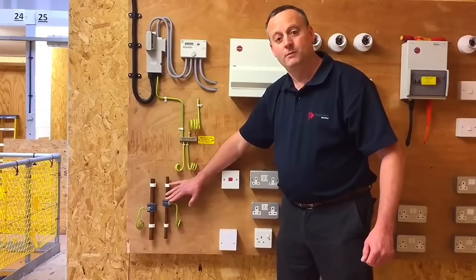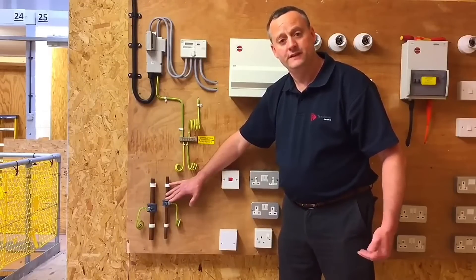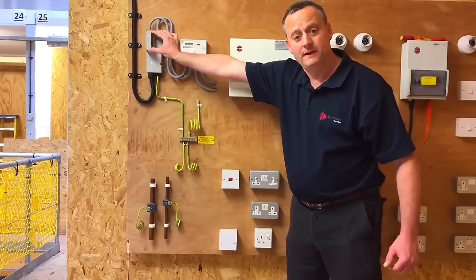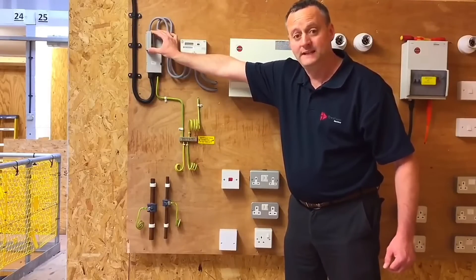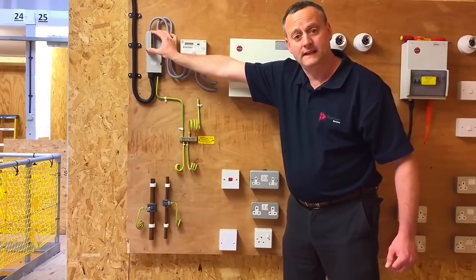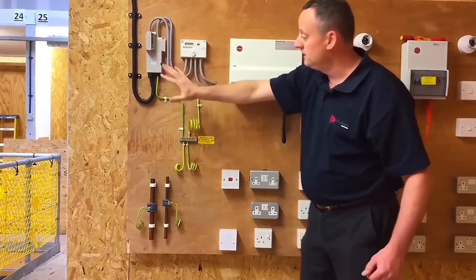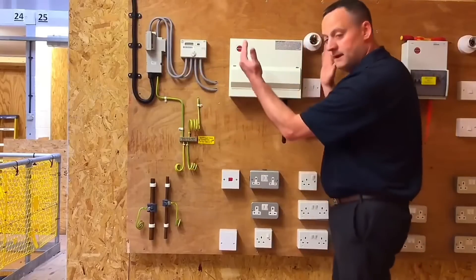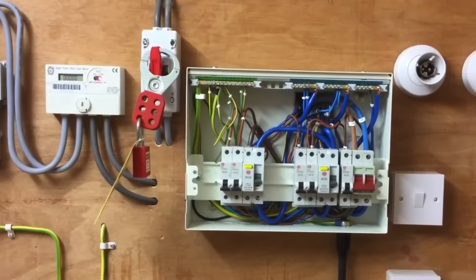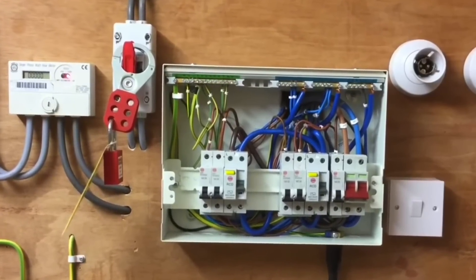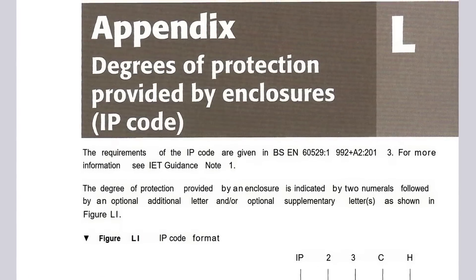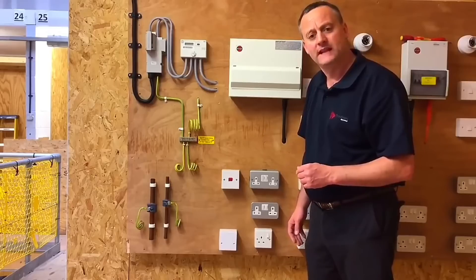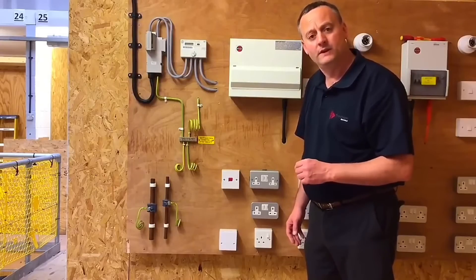In order for ADS to apply, we need the appropriate fuses in the appropriate places. The fuse in the incoming cutout is 100 amps — it could be 80 or 60. We've got a 100 amp cutout fuse, 25mm² tails, 16mm² earthing conductor entering our consumer unit. Before entering, I want to confirm the IP rating. IP stands for Index of Protection or International Protection — both of those can come up in our exam, both for what IP stands for.